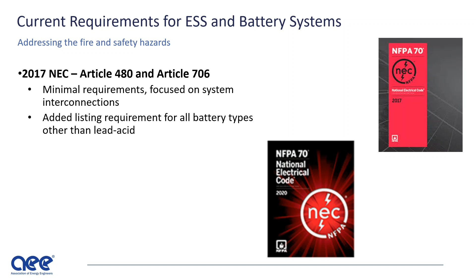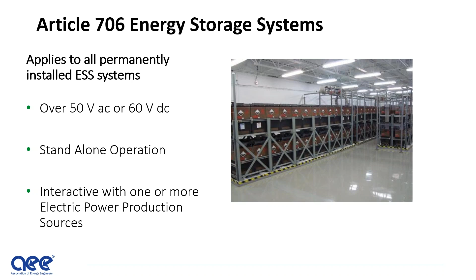For Article 706, which is the key energy storage system article in the National Electric Code, it applies to all permanently installed systems. It operates at either 50 volts AC or 60 volts DC. It's a standalone operation, and it's interactive with one or more electric power production sources. That means it could be operating with a utility system as some type of backup, with a generator, with photovoltaic solar panel systems, or with wind. There has to be some other interactive power production source because you have to be able to generate and recharge the system, whether it's batteries or some other energy storage method.